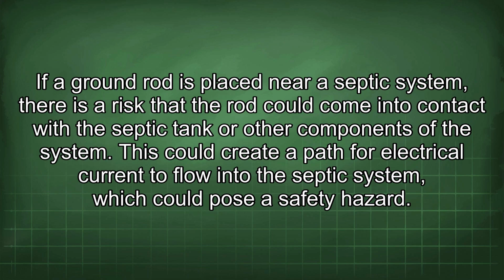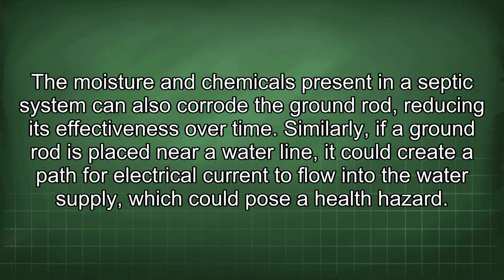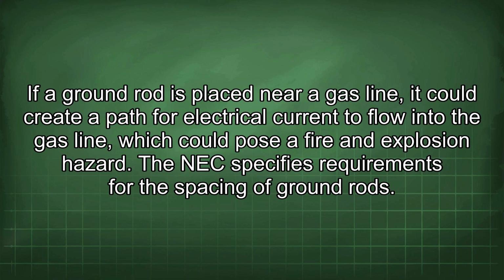and corrosion. If a ground rod is placed near a septic system, there is a risk that the rod could come into contact with the septic tank or other components of the system. This could create a path for electrical current to flow into the septic system, which could pose a safety hazard. The moisture and chemicals present in a septic system can also corrode the ground rod, reducing its effectiveness over time. Similarly, if a ground rod is placed near a water line, it could create a path for electrical current to flow into the water supply, which could pose a health hazard. If a ground rod is placed near a gas line, it could create a path for electrical current to flow into the gas line, which could pose a fire and explosion hazard.